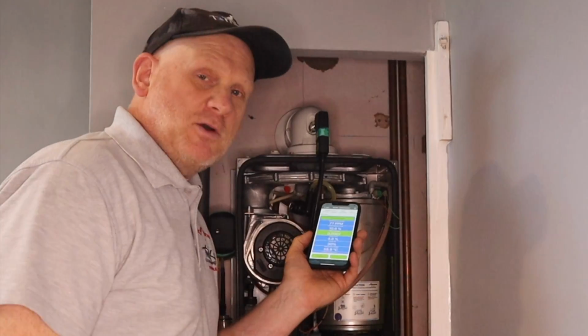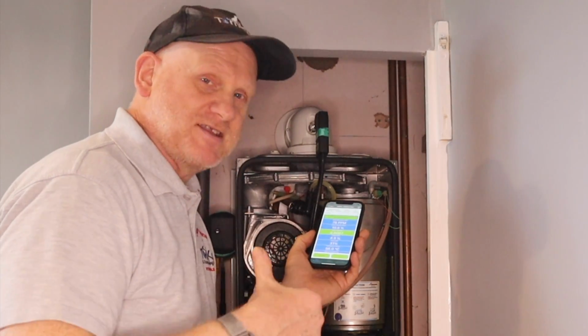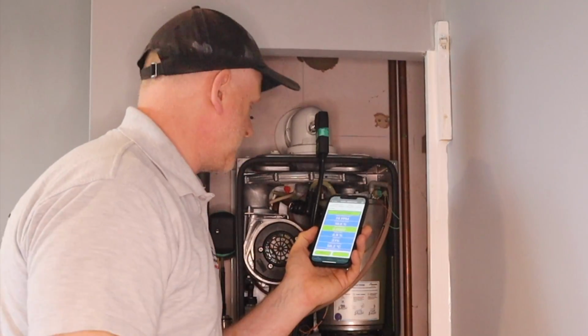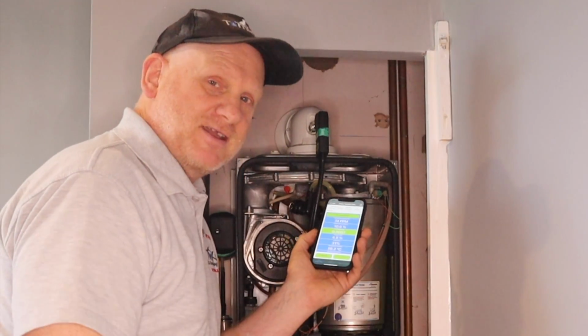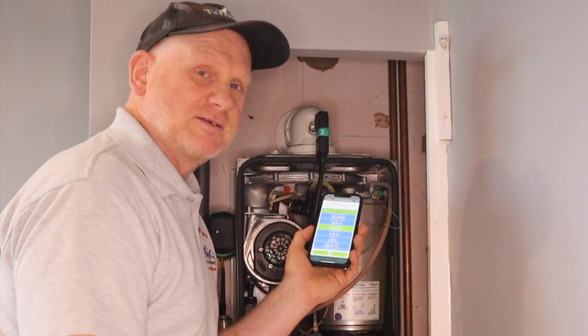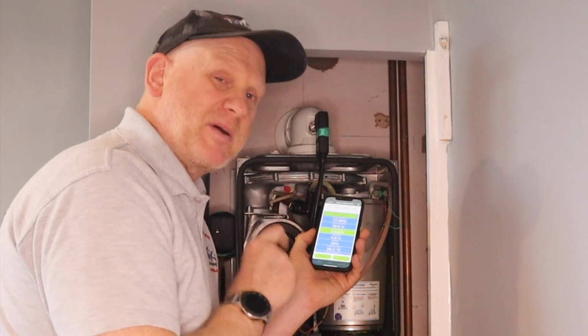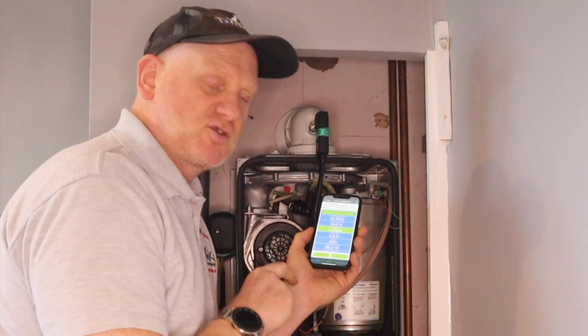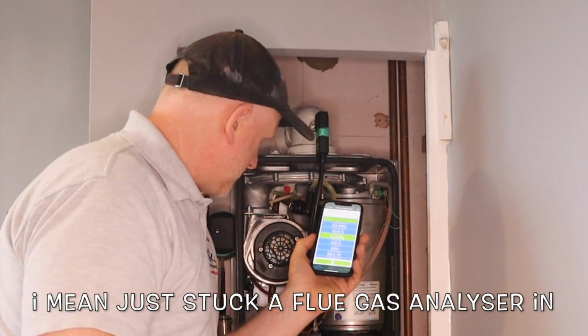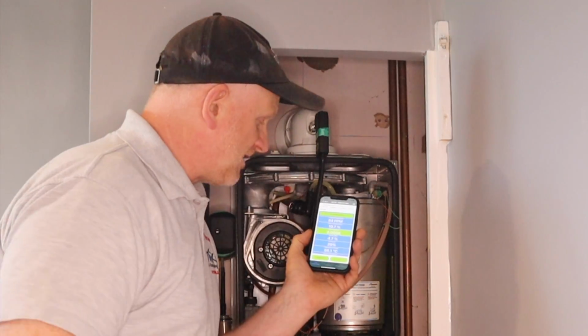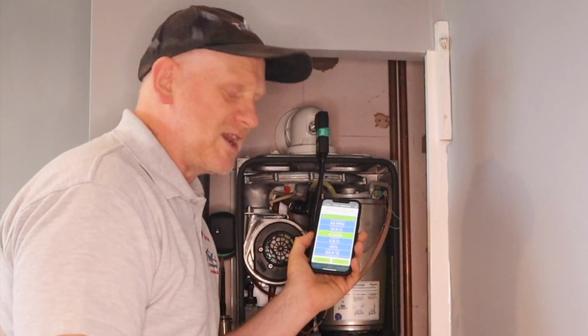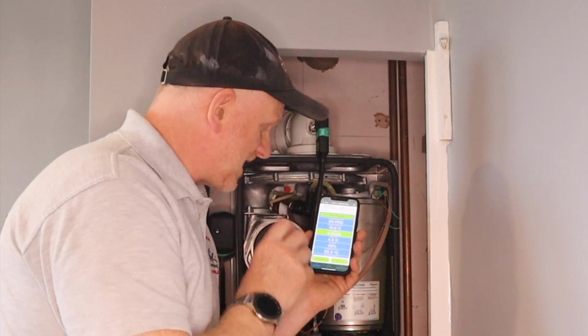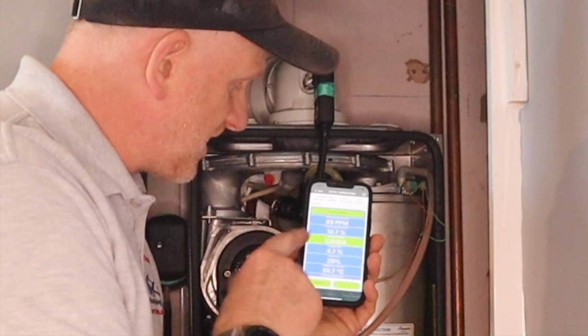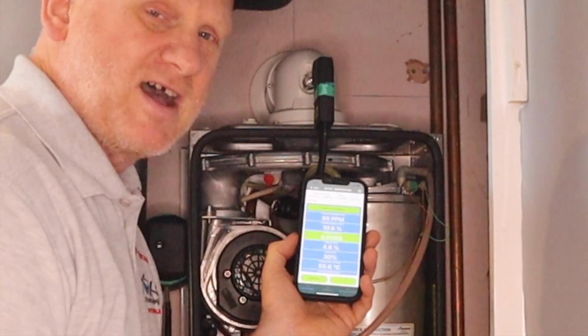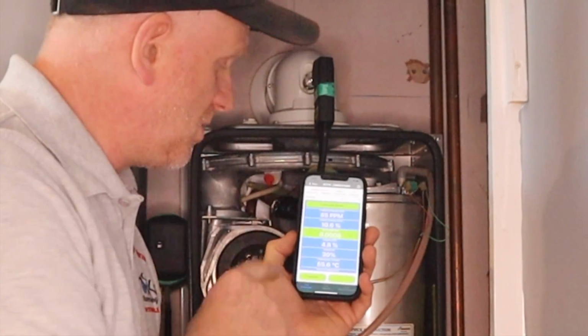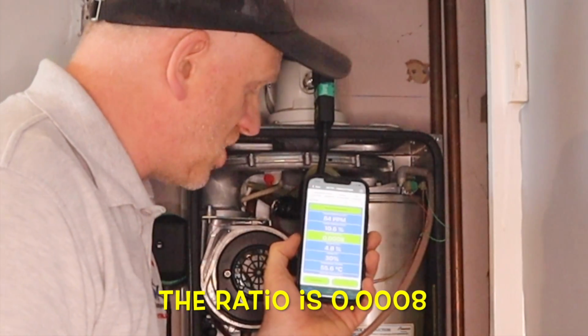Condemned. Now, after the disaster of last night, I've come in this morning, I've stripped it, I've put it all back together again, thinking it's something I've done, but no. I think what's happened is, because that pipe was split, the last person who did service this boiler has played around with the settings on the gas valve. So what I've done is, I've spent a good 20 minutes now getting this set up right on maximum and minimum. So at the moment I've got 10.6, it keeps going between 10.6 down to 10.5. It's on 7 now, CO2 with 85 parts per million and a ratio of 0.0008.